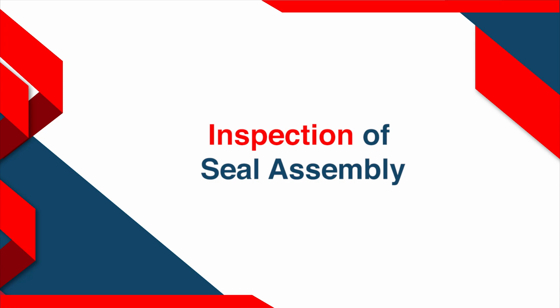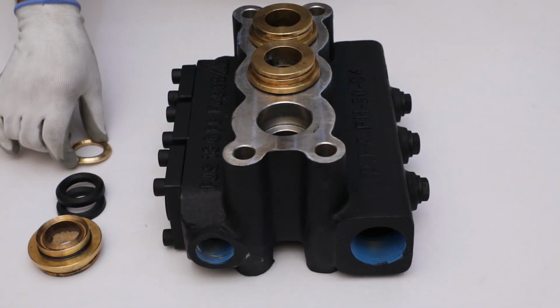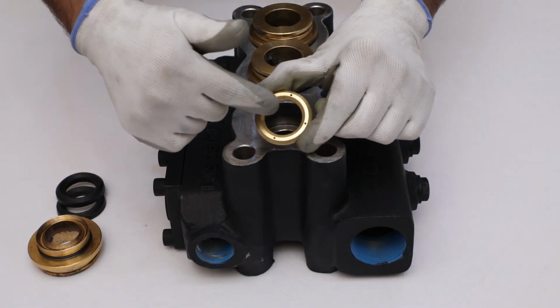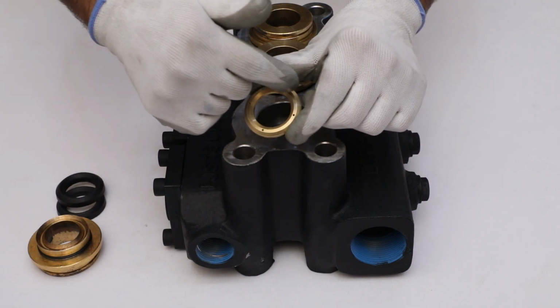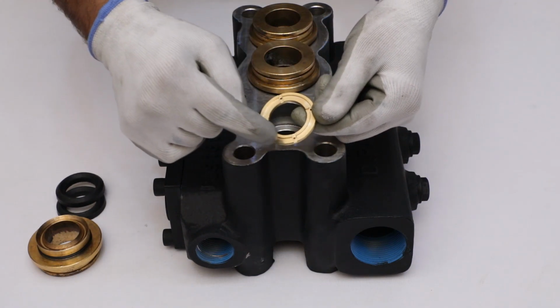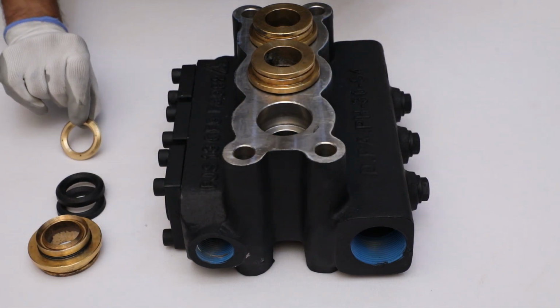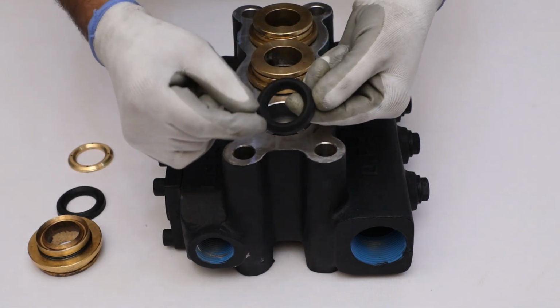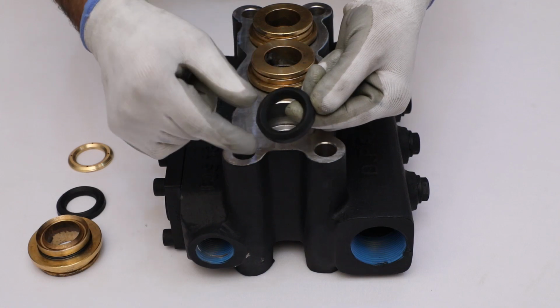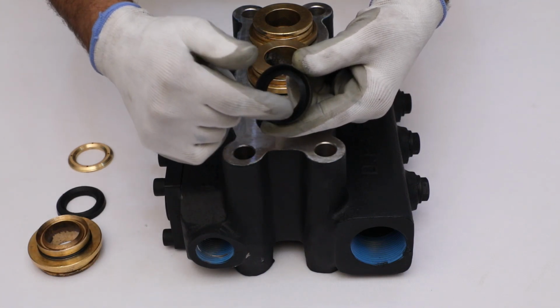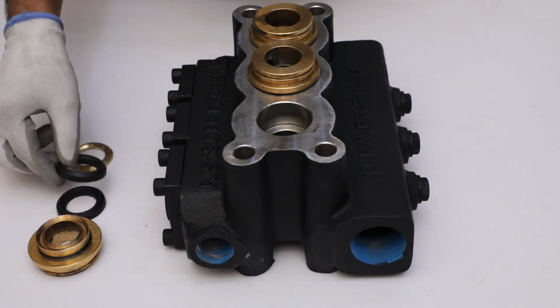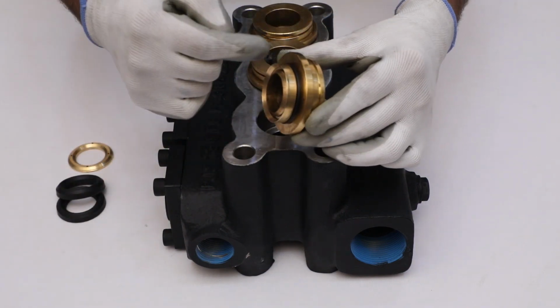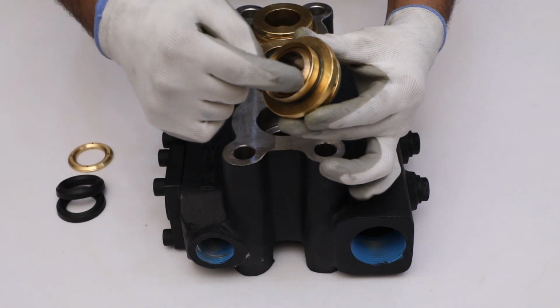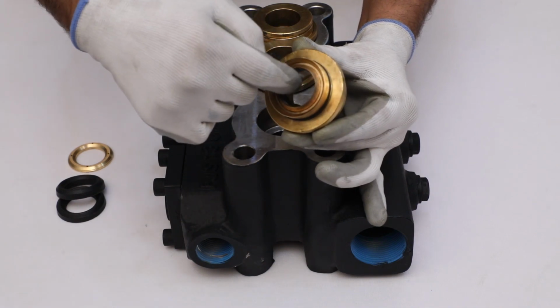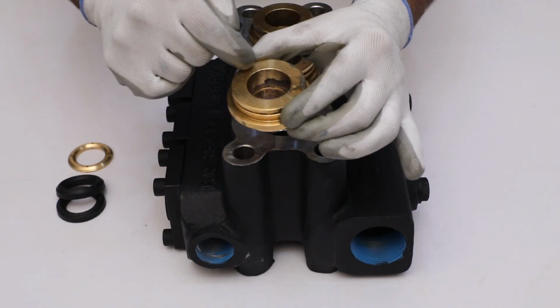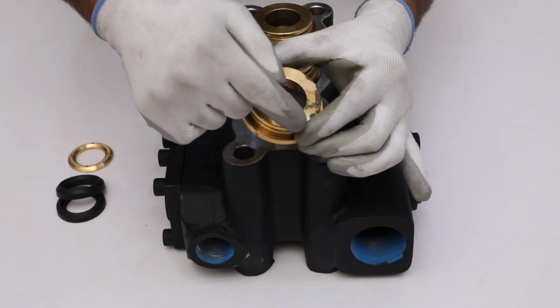Inspection of seal assembly. Check inner and top surface. Also, check the surface having a groove of packing ring for damage or dent mark. Inspect all surface of chevron type plunger seals for any damage. Now, take packing support and look into groove of plunger seal and inner surface and top flat surface for any damage or wear.